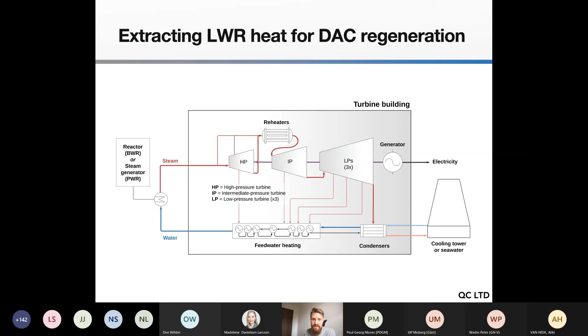This is a picture of a typical turbine building cycle, based on the EPR. HP means the high pressure turbine, where the steam comes in first, IP the intermediate pressure turbine, LP the low pressure turbines, and the red arrows and lines here are steam at various qualities, and the blue is liquid water. So what we want to do is tap in at 1 or 2 or 3 or more of the appropriate locations in the steam cycle, extract some of that steam out to a condensing heat exchanger, condense that steam into water, and then pump that water back into the feed water heating system at some appropriate location, while not impacting the safety case or the overall operation of the nuclear plant.